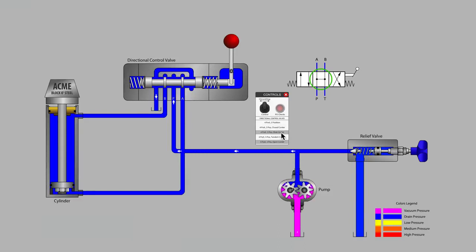Here's a tip. It is not important to memorize the common names for these valve centers such as float or tandem or open. If you are working with a hydraulic component vendor or a customer that has hydraulic machines, simply referring to which ports are connected together and which ports are blocked at the center position is usually more than adequate and often the more accurate way to communicate.